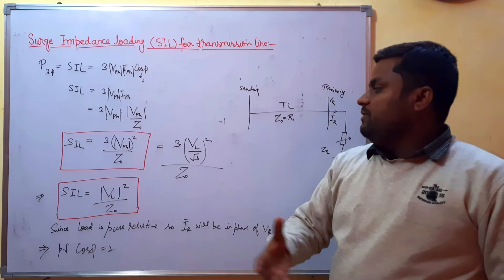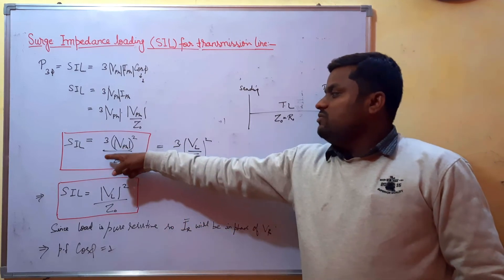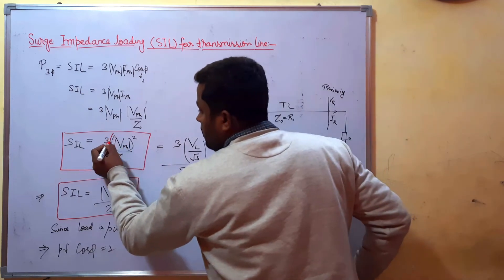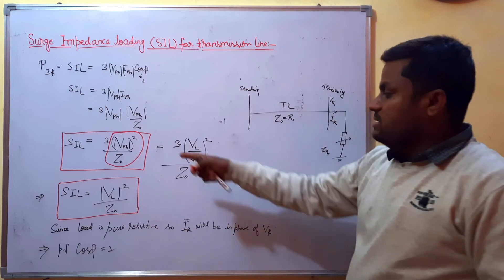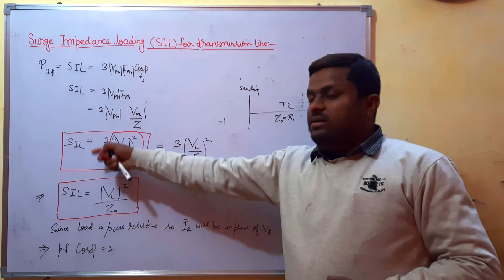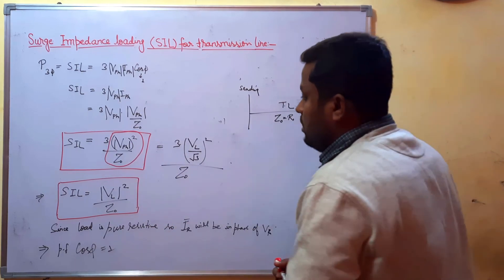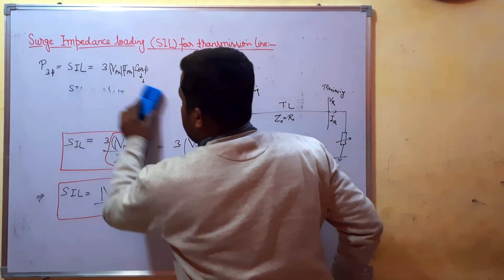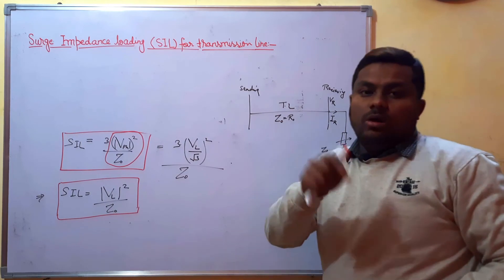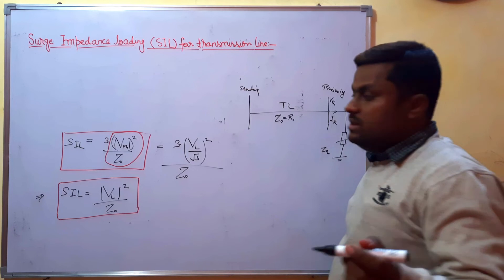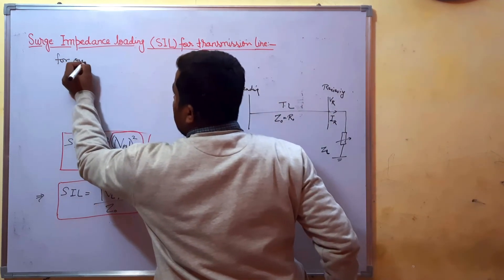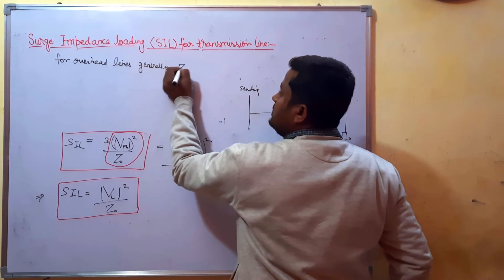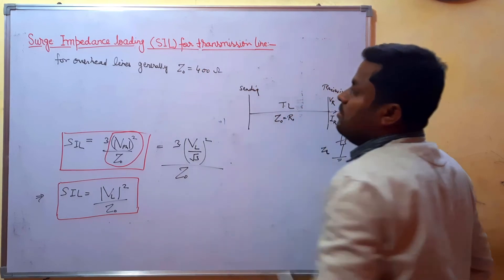If voltage is considered as phase voltage, the per-phase formula applies, and multiplied by three gives the total SIL. If expressed in line voltage, SIL = VL² / Z0. For lossless overhead transmission lines, the value of Z0 is typically equal to 400 ohms.